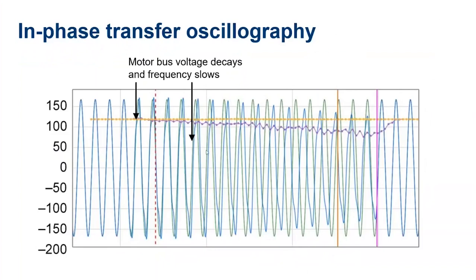We have again the two signals. The blue one is the one from the bus, the green one is the one from the feeder we are trying to transfer to. And we also have here the voltage magnitude because we are checking for that. And so we see the yellow horizontal here, that the magnitude of the other feeder is healthy, and the voltage magnitude at the bus going down as time goes by, and the motors spin down.